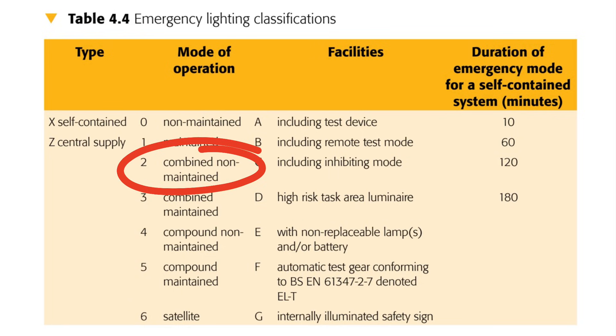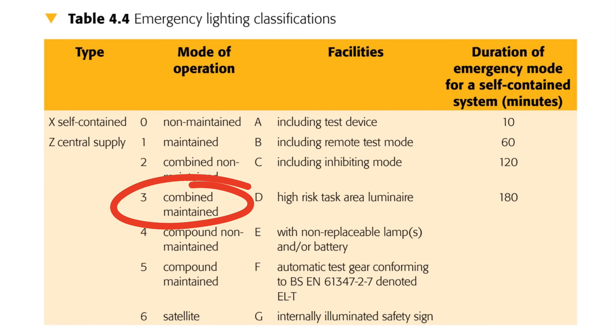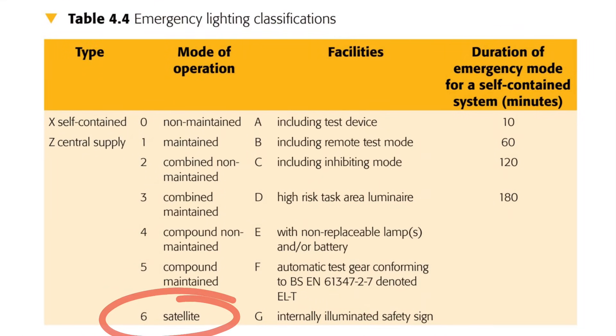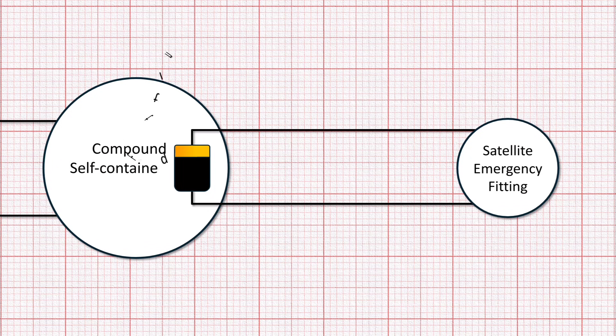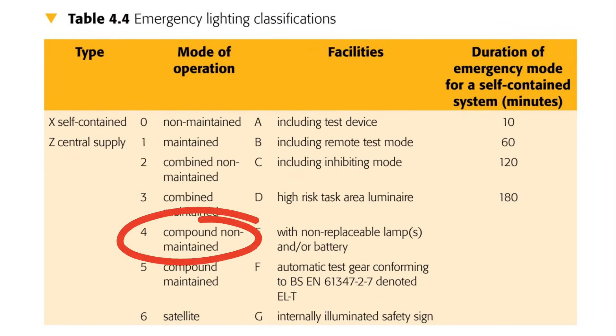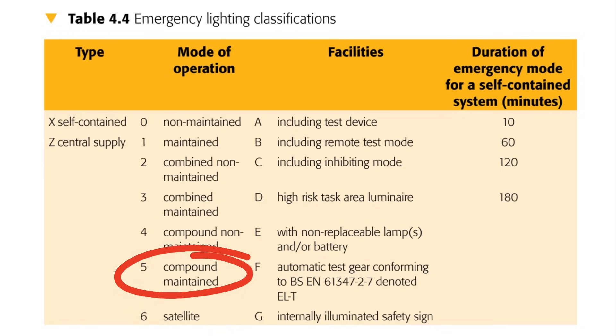Mode of operation two is combined and non-maintained. Mode of operation three is combined and maintained. Skipping ahead to number six, this is what's referred to as satellite — where an emergency light fitting doesn't have a battery backup inside itself, but rather derives its emergency supply from another fitting. The fitting it gets its supply from is referred to in modes four and five as compound self-contained emergency fittings. Number four is compound non-maintained, and number five is compound maintained.